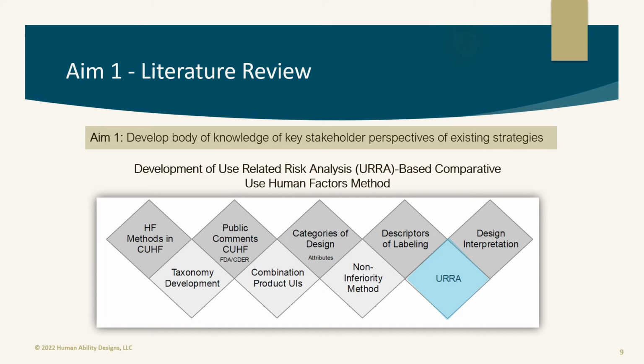The URRA is pretty standard practice at this point in FDA submissions, and it really serves as the backbone of the human factors validation study and brings the context of use-related risk into the task analysis. So the main secret I'm sharing today is that if there's no URRA comparison in the comparative use method, then there's really no way the human factors analysis can be complete.